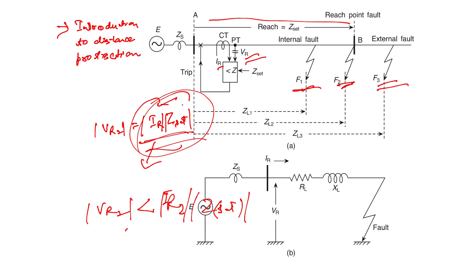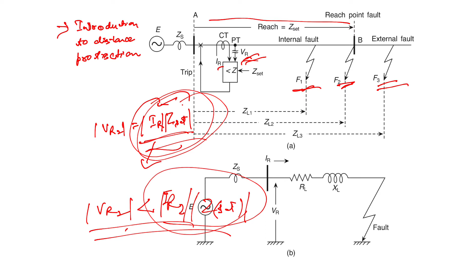And if VR is greater than IR into Z set, then definitely it will not trip. So we found a trip law. What is the trip law? The trip law is that if VR is less than IR into Z set, then the signal is trip, and else it will restrain.